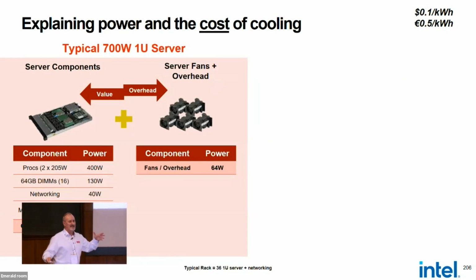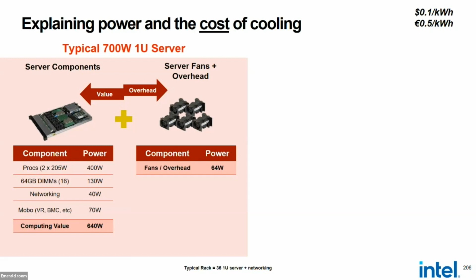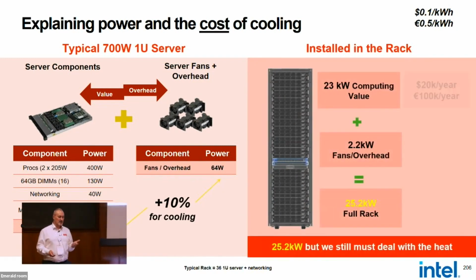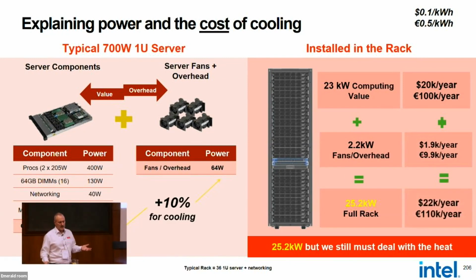Let's translate that into numbers. A 700 watt 1U server has a computing value of about 640 watts, with fans consuming about 64 watts — roughly 10% of that platform. Taking into account 10 cents or 50 euro cents per kilowatt hour, a typical 23 kilowatt rack actually requires 25.2 kilowatts of connectivity and power due to the fans. Financially, that translates to about 22K in the US, which is more reasonable compared to 100K in Europe with 50 cents per kilowatt hour in some countries — Germany is extreme at the moment. But you see the overhead that fans alone create on the infrastructure.